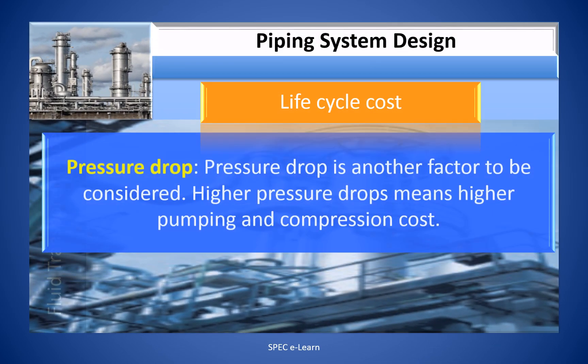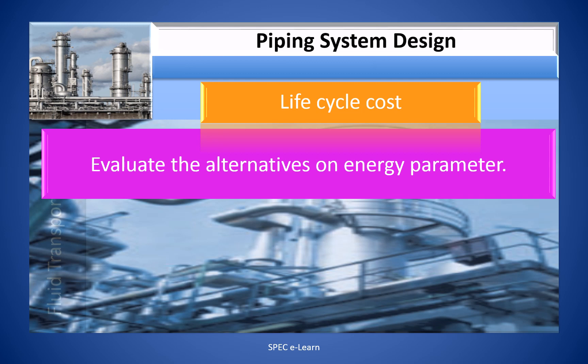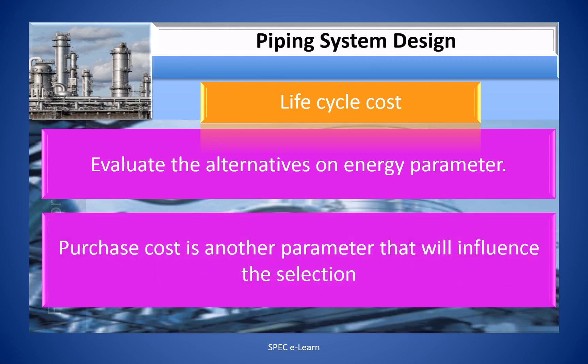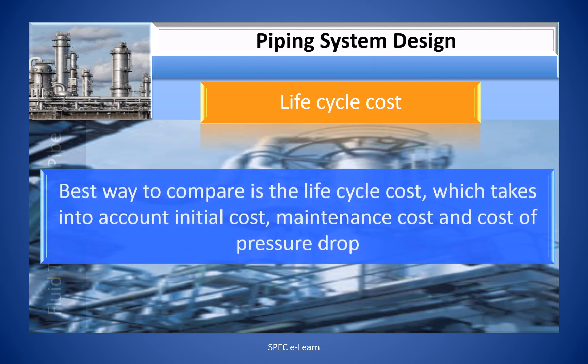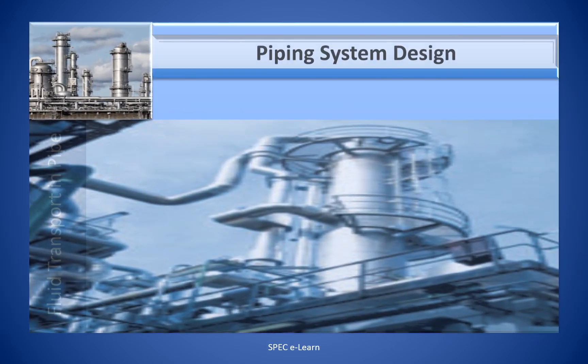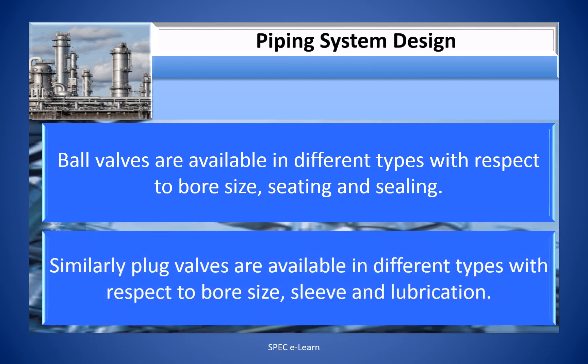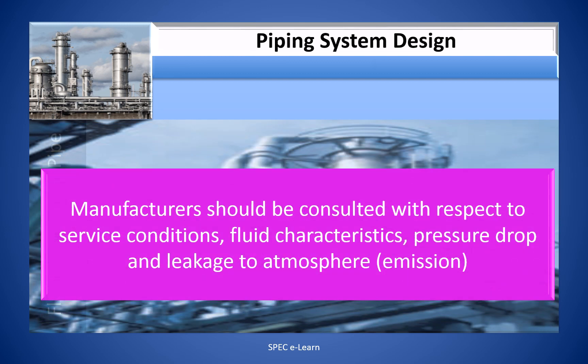Pressure drop is another factor to be considered. Higher pressure drop means higher pumping and compression cost, so evaluate alternatives on an energy basis. Purchase cost is another parameter that influences selection. The best way to compare is life cycle cost, which takes into account the initial cost, maintenance cost, and cost of pressure drop. Ball valves are available in different types with respect to bore size, seating, and sealing. Similarly, plug valves are available in different types with respect to bore size, sleeve, and lubrication. Manufacturers should be consulted with respect to service conditions, fluid characteristics, pressure drop, and leakage to atmosphere (i.e., emissions).